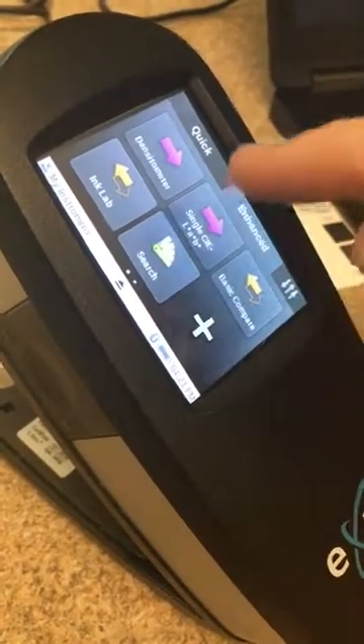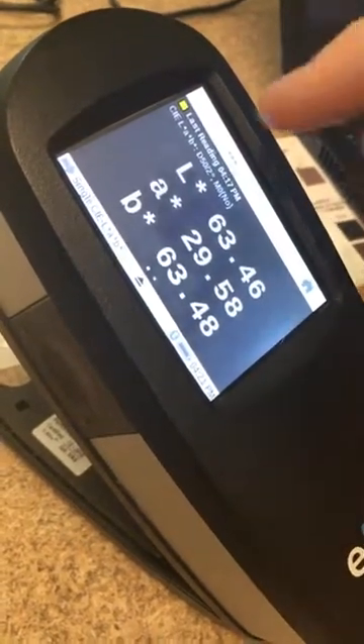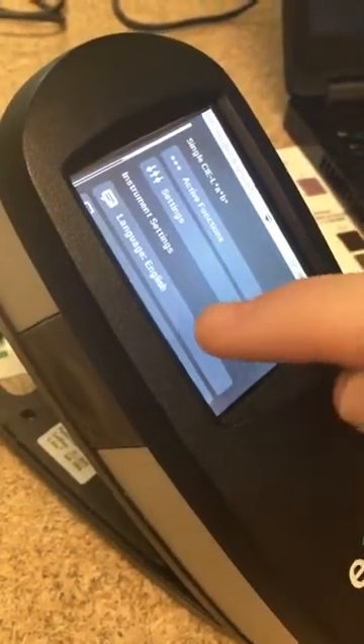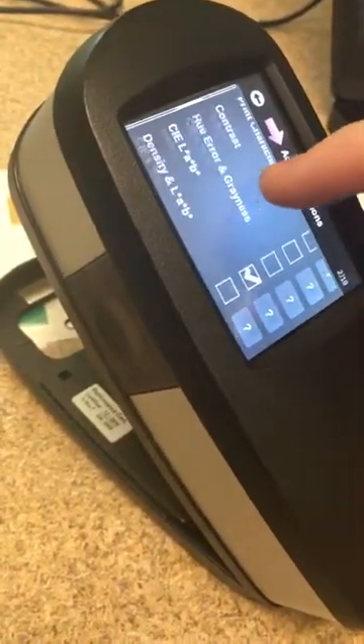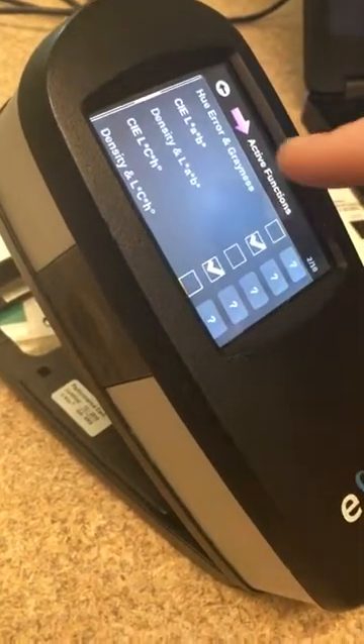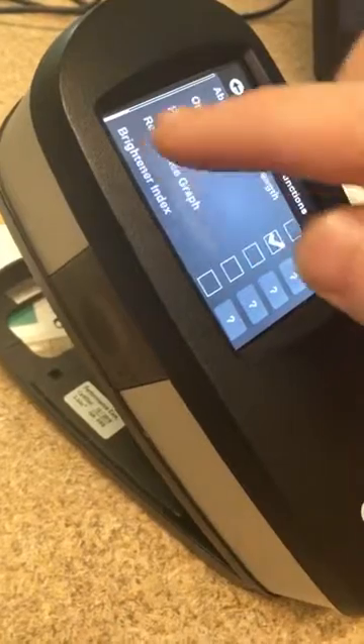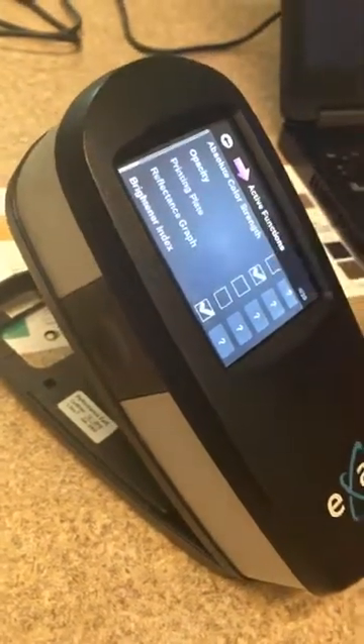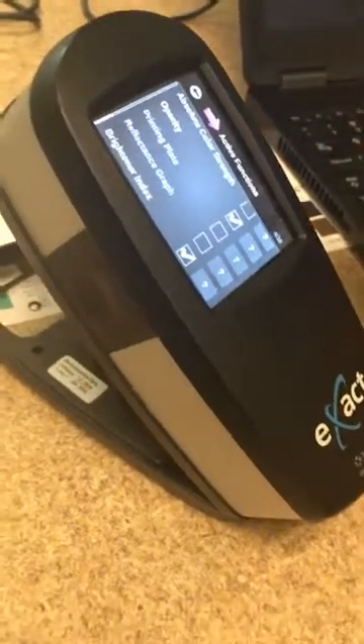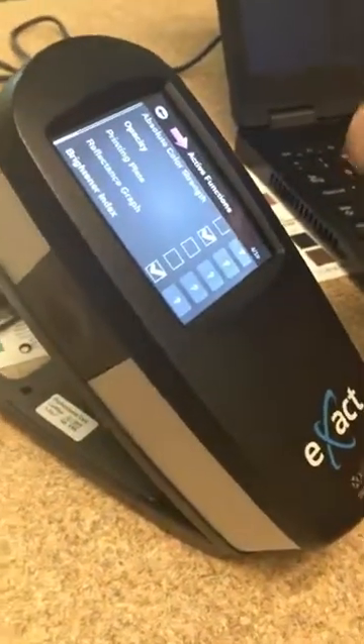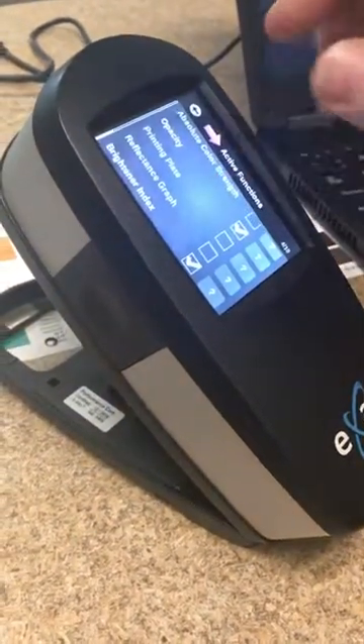Going into the Single LAB function — if I want to take a LAB reading, this is where I go. Using that arrow brings up active functions and settings. Active functions allows me to turn on or turn off different attributes I want to see on screen. I can turn on LAB, turn off LCH, turn on paper indices and opacity. There's also something new called the brightness index, which requires the new firmware and M1 simultaneous mode. It uses M1, M0, and M2 calculations to look at the B value and determine how much OBAs are in your paper stock.